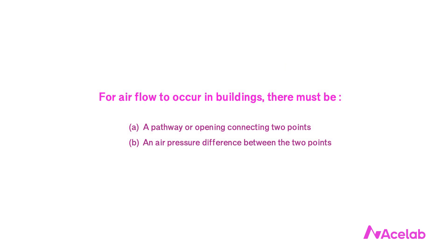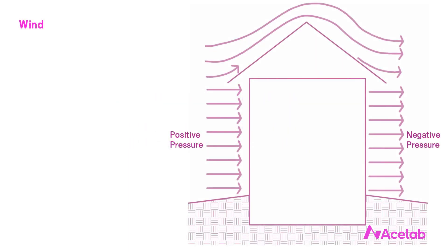For airflow to occur between two points — say the outside and the inside — there must be a pathway or an opening connecting those two points and an air pressure difference. Both of these conditions must exist. If we have a pathway but no pressure difference, we won't have airflow. If we have a pressure difference but no pathway, we won't have airflow either. In practice, it's very difficult in building design to eliminate or perfectly seal all of the pathways. Pressure differences are generated by wind, temperature, and mechanical equipment.